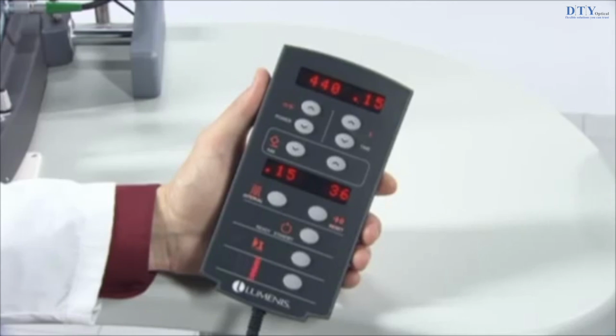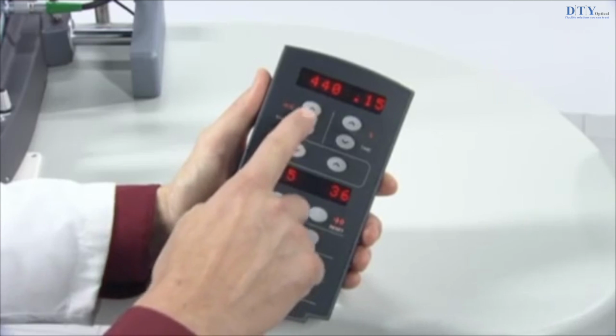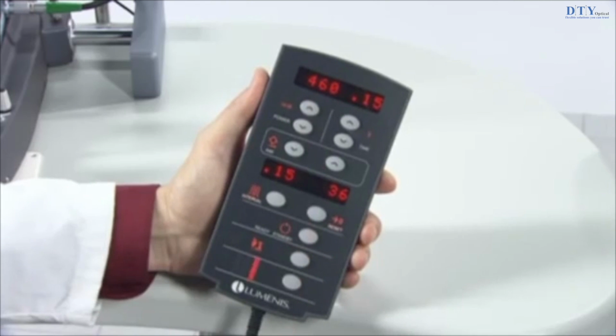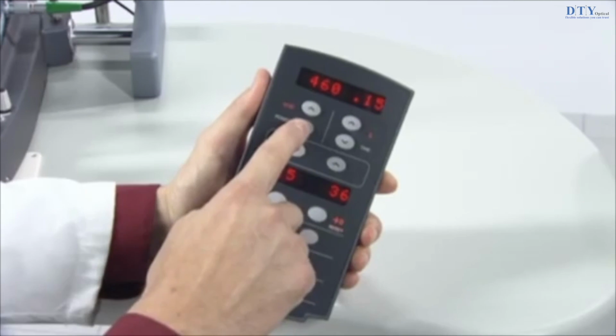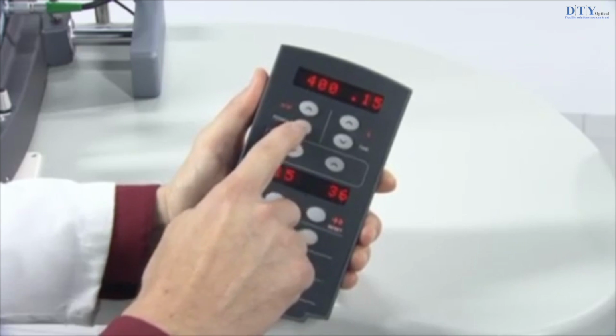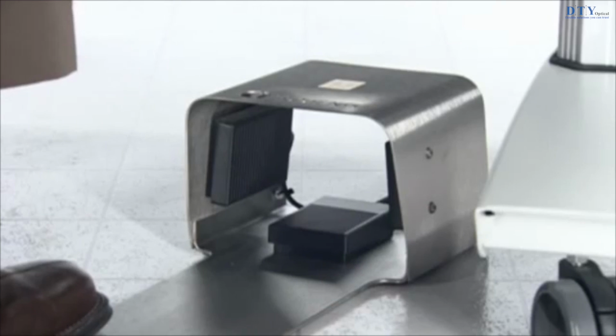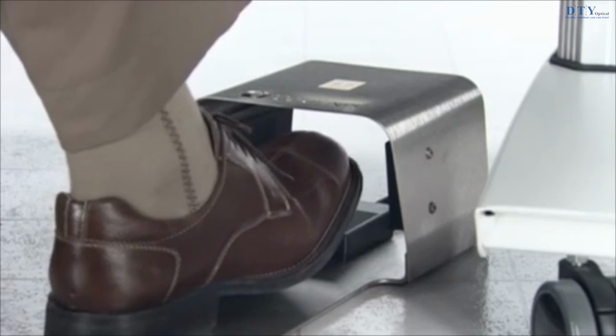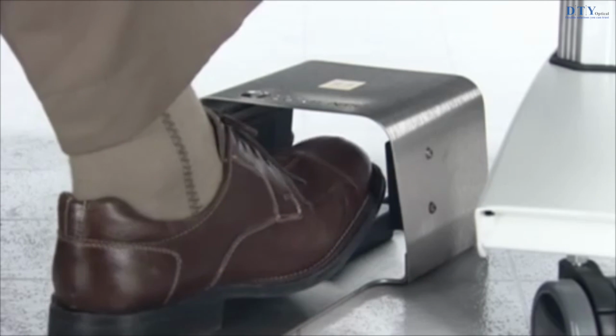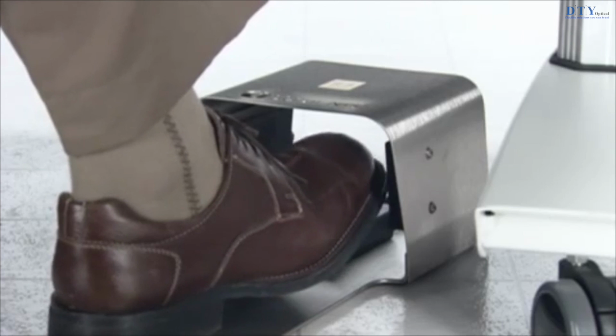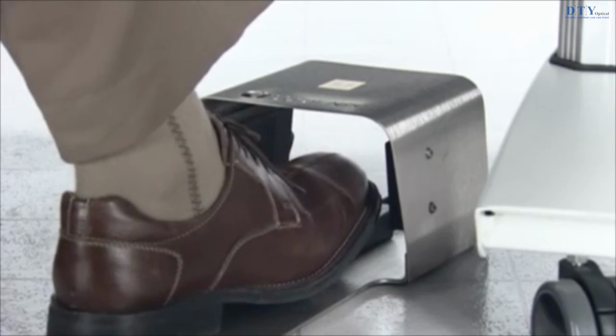To set the power from the remote control, press the up increase and down decrease selectors in the field until the desired setting displays. If you are using the Power Ease foot switch, you can also adjust the laser power by pressing the switches on the inside of the foot switch housing: left to decrease power and right to increase power.